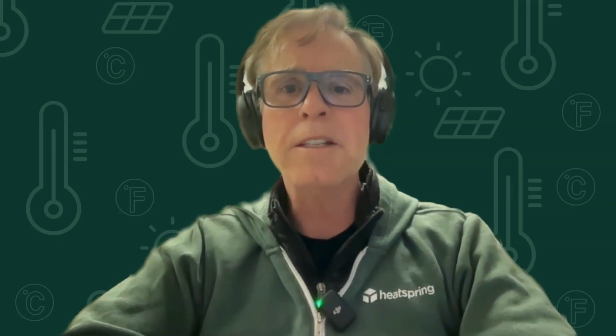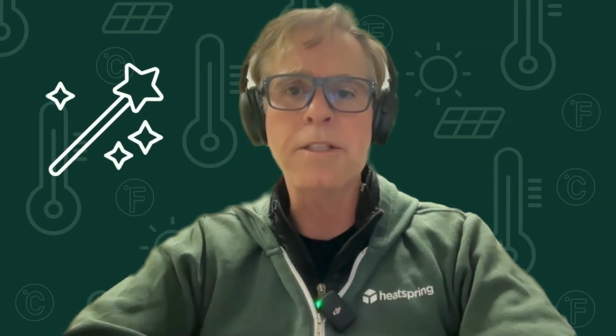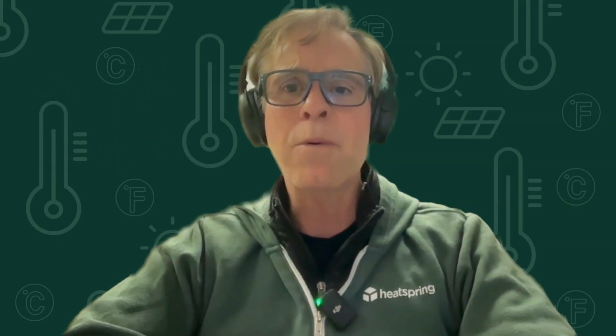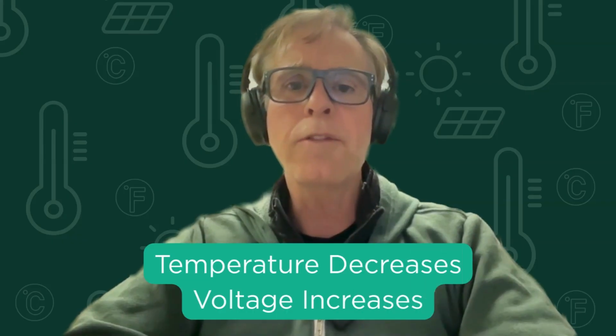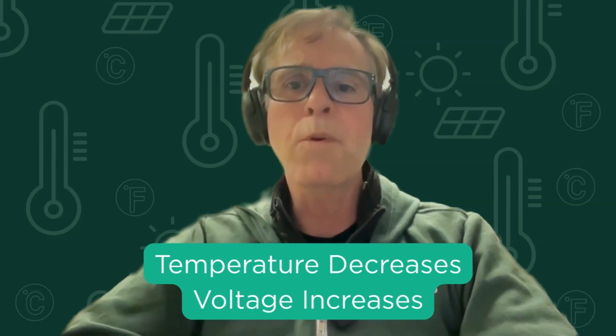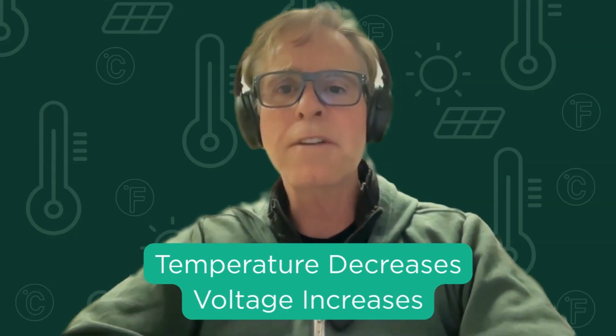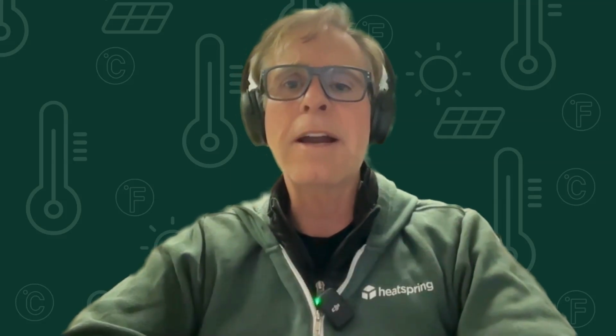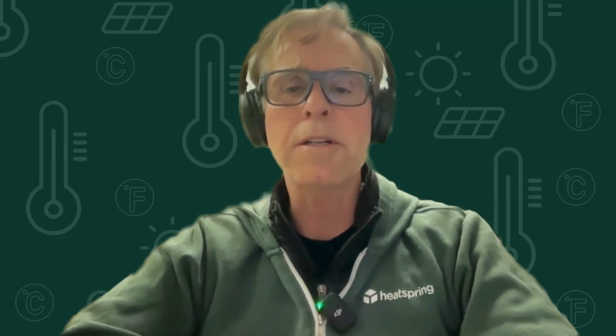And one of the weird things about these magic crystals, otherwise known as solar cells, is that when it gets colder, the voltage goes up. So if you live in a really cold place, you're going to have to do a different calculation to figure out how many solar modules you can put on a string.